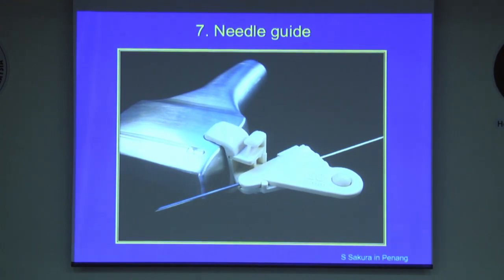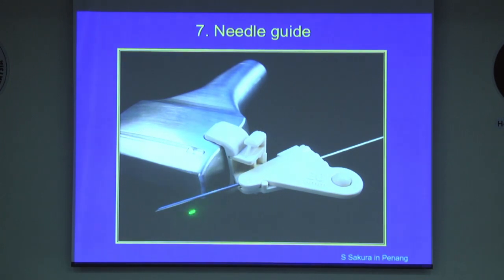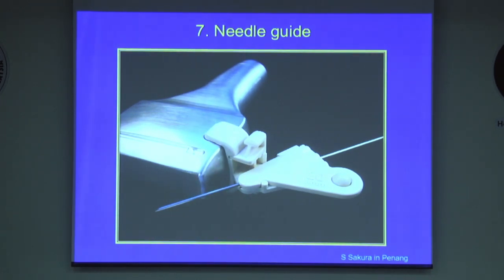Another solution could be the use of a needle guide. Needle guides fix the needle in position relative to the transducer so that it can prevent the needle from deviating from the beam while the needle is being advanced. You can imagine that this can increase the image quality, especially for inexperienced operators.